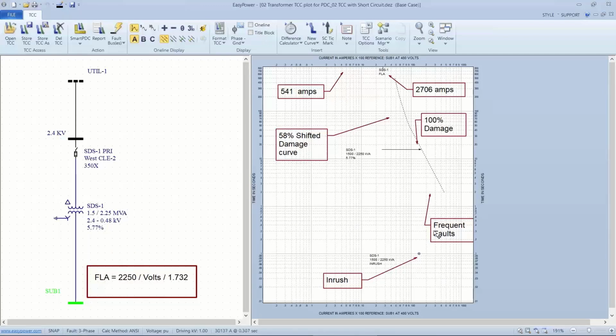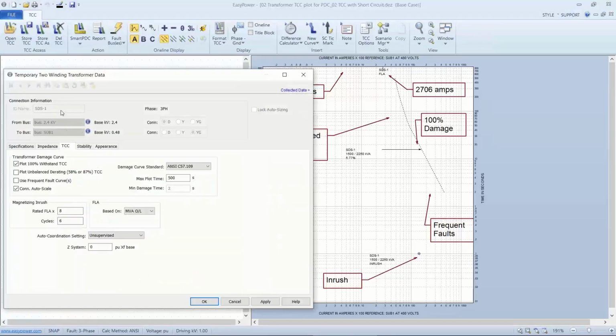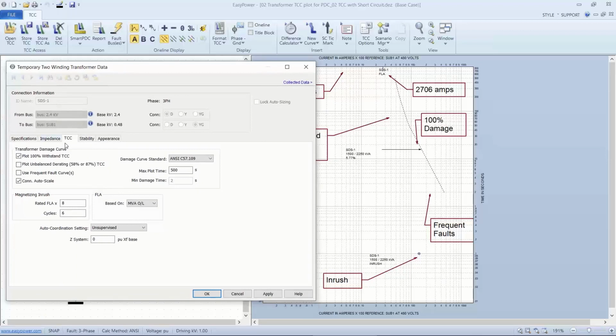Now, although I have my notes in here, I'm not displaying the frequent faults or the 58% derated damage curve. We are showing the inrush, which is a factor of the parameters that have been entered in the setup for the two-winding transformer under the TCC curve. The magnetizing inrush in this case is being plotted at 8 times full load current and 6 cycles. Now, if we wanted to adjust that, if we wanted to see what the difference would be with, let's say, 12 times full load rating, you can see that plot moves to the right, and that will have an impact on protective devices that have sensitivity at this particular time point. And again, these can be set by supervised and unsupervised selection. We've selected the ANSI standard C57.109 for the plot of the curve, the definition of the curve.